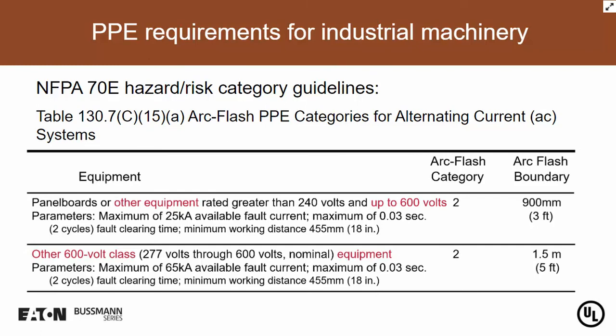kA with an opening time. So the overcurrent protection device must open within 2 cycles, or 0.03 seconds. A lot of times we don't know what the opening time would be. But this is the chart that we would use if the arc flash hasn't been calculated and there hasn't been a sticker that shows me what PPE to wear. I wear a minimum then of PPE 2, which again is the 8-calorie suit and so on.